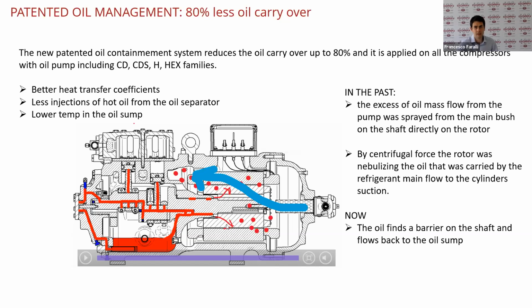With the new design, which is quite a simple design feature, the oil is locked in this part, and it's like a barrier, and so the oil, instead of leaving from this side, is forced to come back 100% to the oil sump. We started introducing this feature in our CO2 compressor, and when we saw that the results were quite impressive, with up to 80% less oil carryover, we introduced the same feature on our ATEX family and also on the standard Freon.